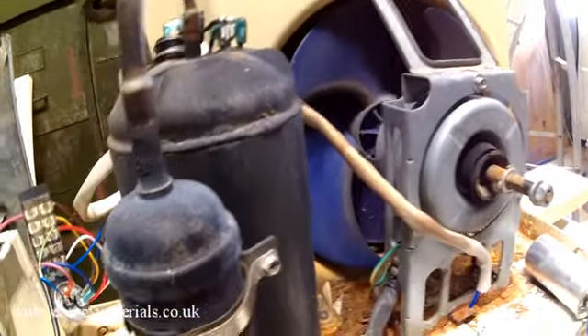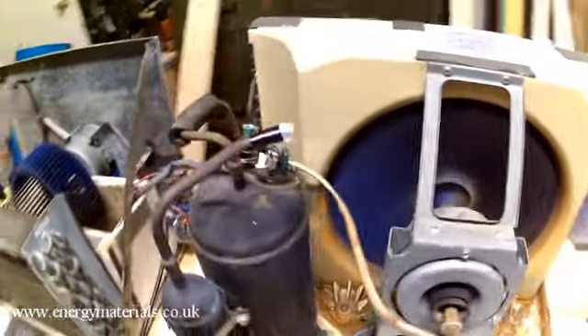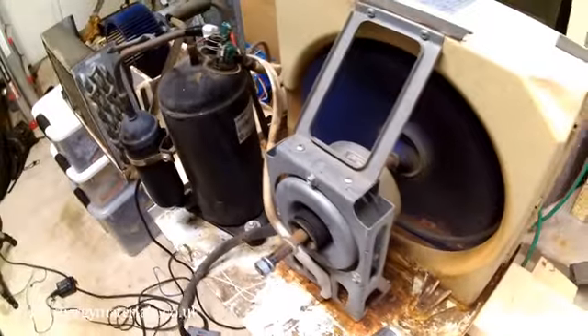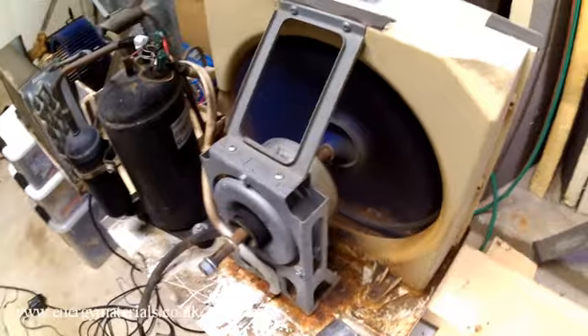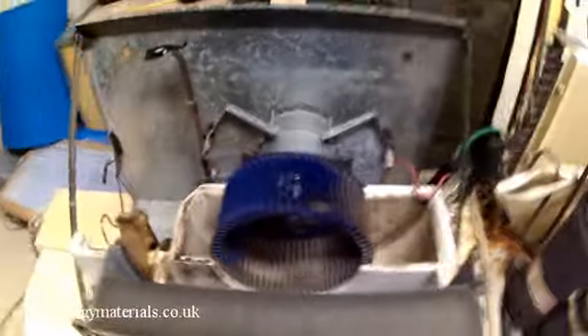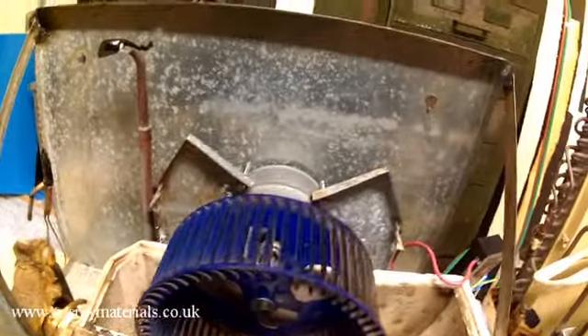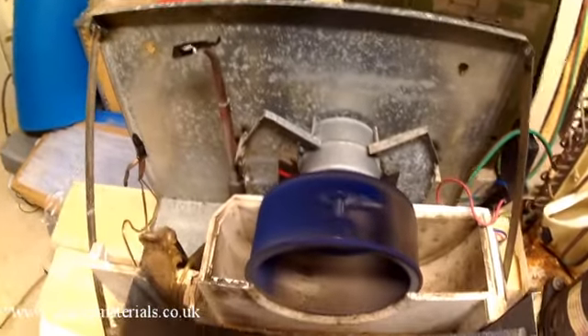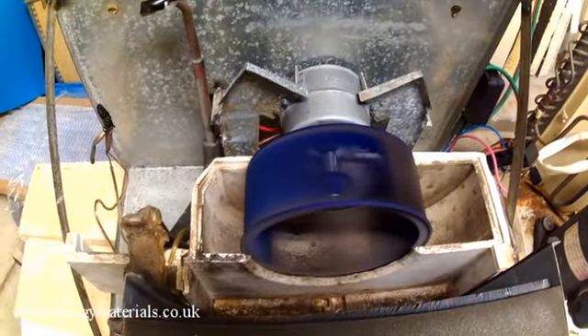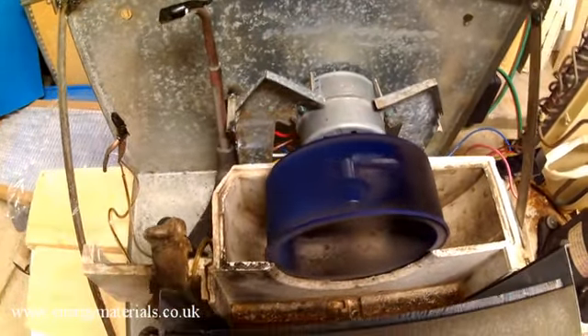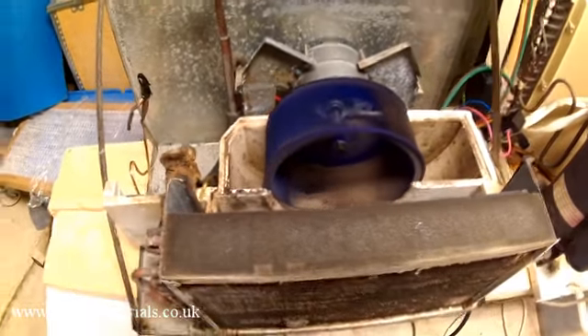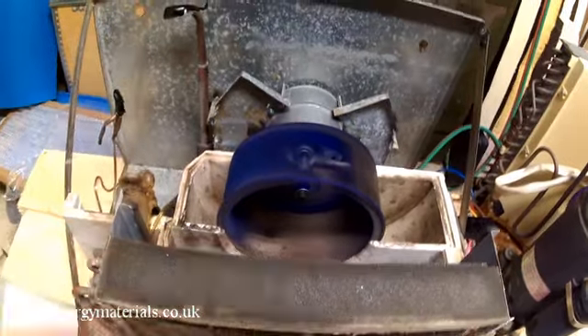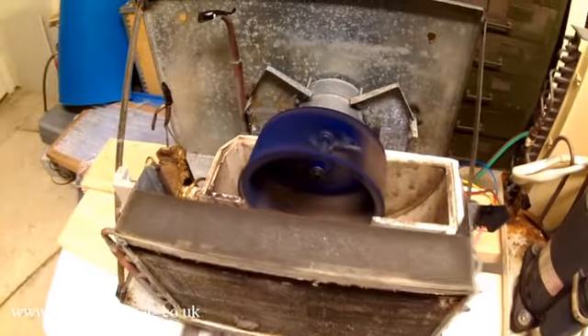So let's switch on the power to the condenser. And sure enough, that fan blows. So that should do the cooling outside of the house. And then let's switch on the radial blower. And yep, sure enough, stuff is doing some blowing. So hopefully we should be good. So this should be cycling through the evaporator, blowing out and returning through the cowling back into the garage. Excellent.